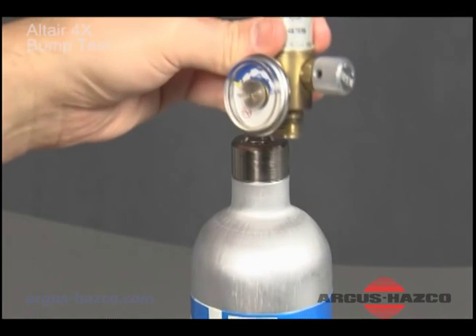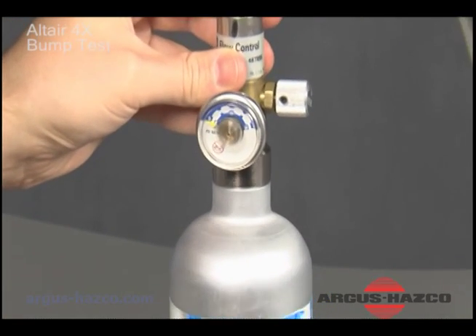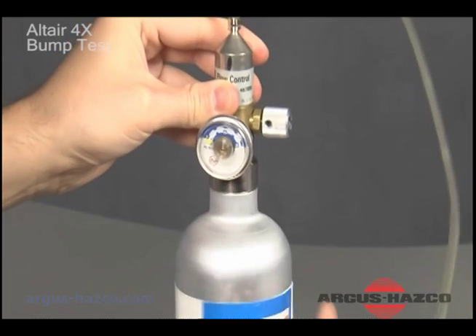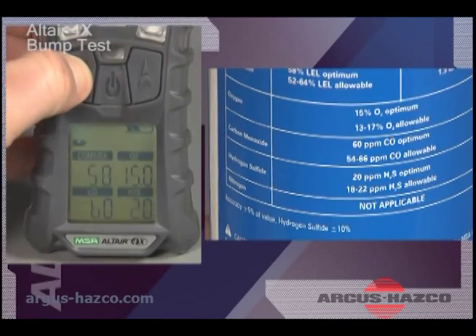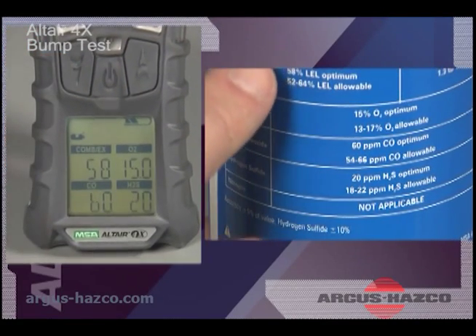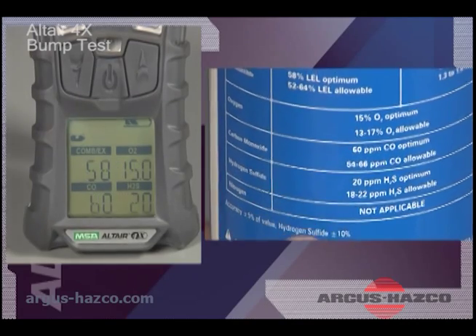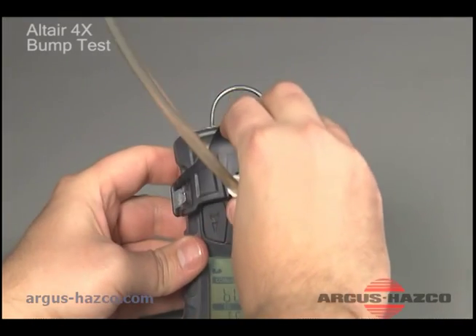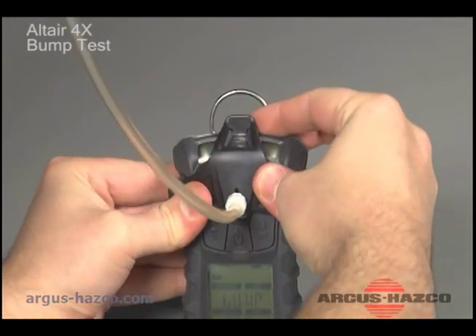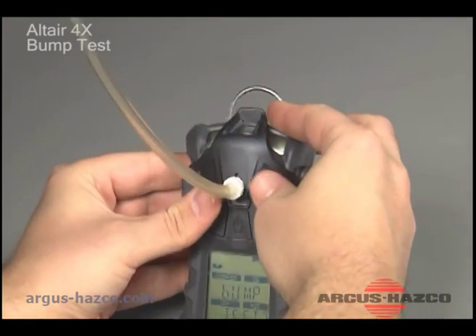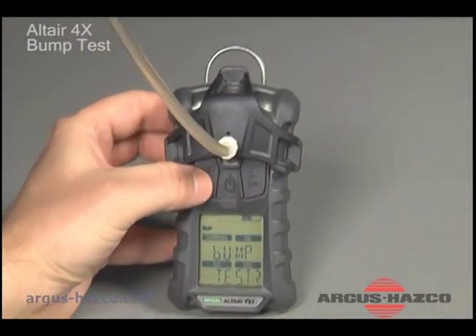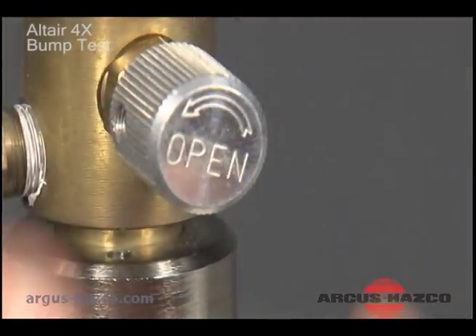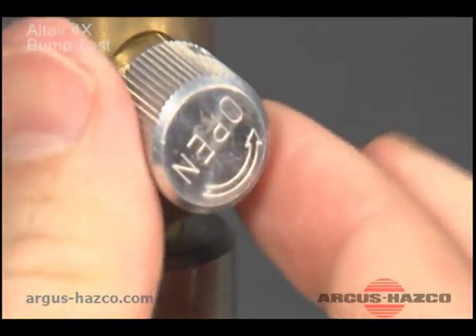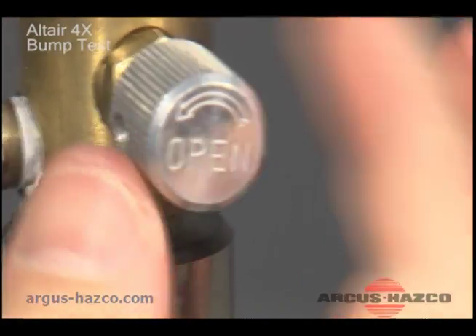Connect the regulator to the cylinder, then connect the regulator tubing to the calibration cap. From the bump test page, verify that gas cylinder concentrations match those displayed on the bump test page. Next, connect the calibration cap to the detector. To start the test, press the Accept button and immediately turn the valve on the regulator to open. After the bump test completes, be sure to turn the regulator valve to the closed position.